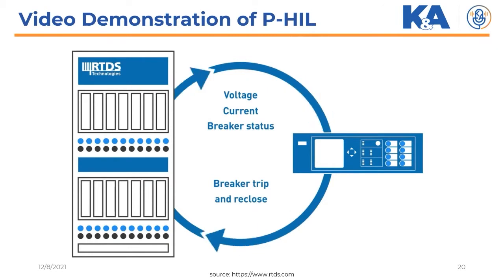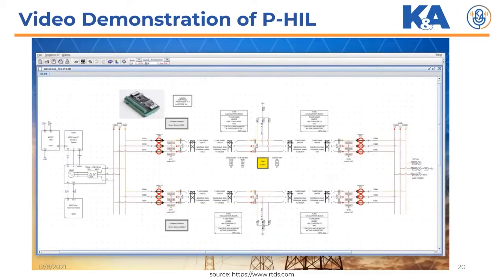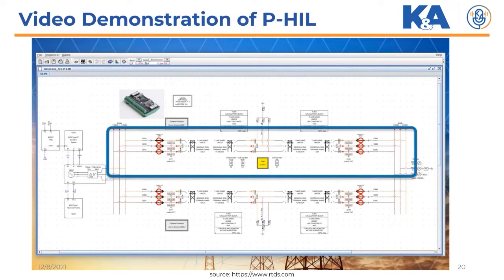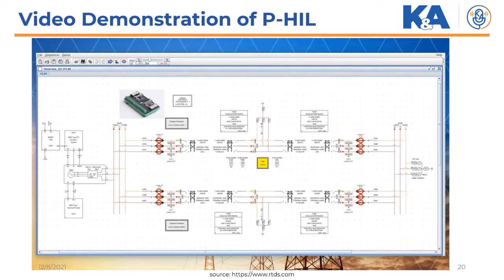Back into the simulation to close the loop. A simulation case has been developed in the draft module of RSCAD for testing the physical distance protection relay. The case includes a transmission line containing a fault branch, the position and resistance of which can be defined and varied by the user from the runtime module. Two circuit breakers isolate the line. On each end of the line are current transformers and capacitive voltage transformers to provide secondary level currents and voltages to protective relays.